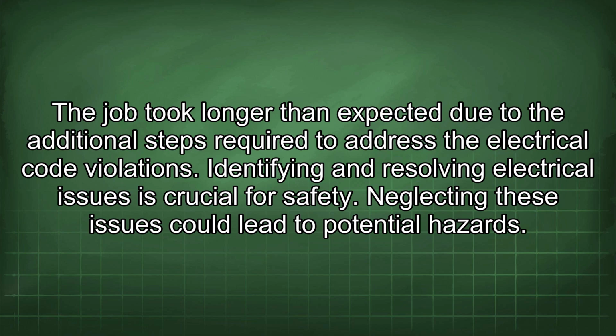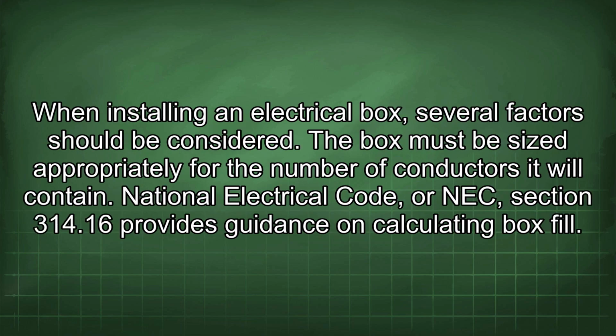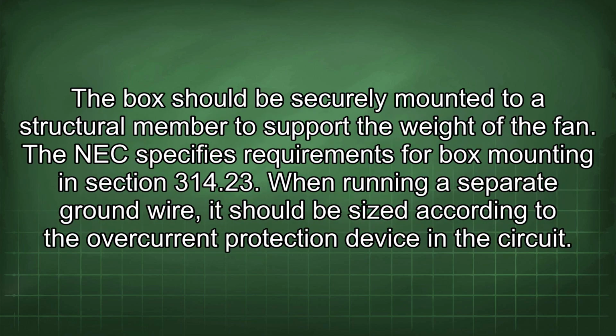Identifying and resolving electrical issues is crucial for safety. Neglecting these issues could lead to potential hazards. When installing an electrical box, several factors should be considered. The box must be sized appropriately for the number of conductors it will contain. National Electrical Code, or NEC, Section 314.16 provides guidance on calculating box fill. The box should be securely mounted to a structural member to support the weight of the fan.